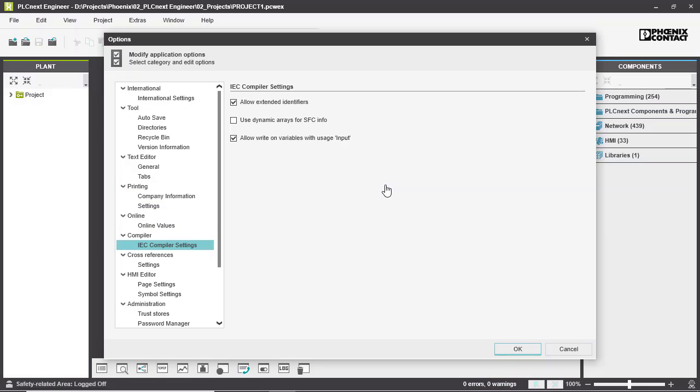The first option in IEC Compiler Settings is Allow Extended Identifiers. Identifiers in general are variable names or instance names. The standard IEC 61131-3 identifiers do not allow using special characters or beginning an identifier with numerical characters. This option extends the use of possible characters in the identifier. But be careful because this option is mandatory for projects that contain extended identifiers and are used in a different instance of PLCnext Engineer.